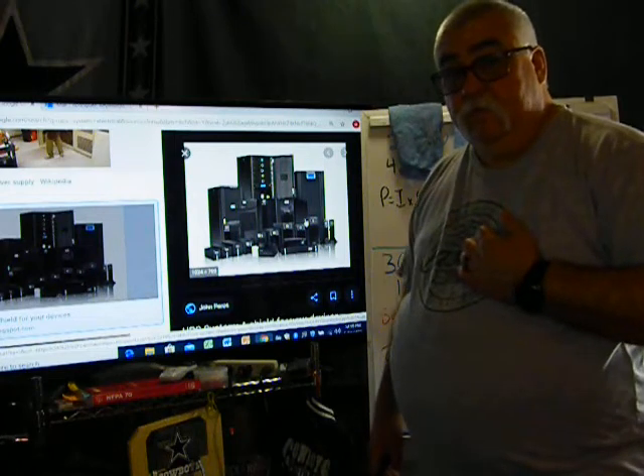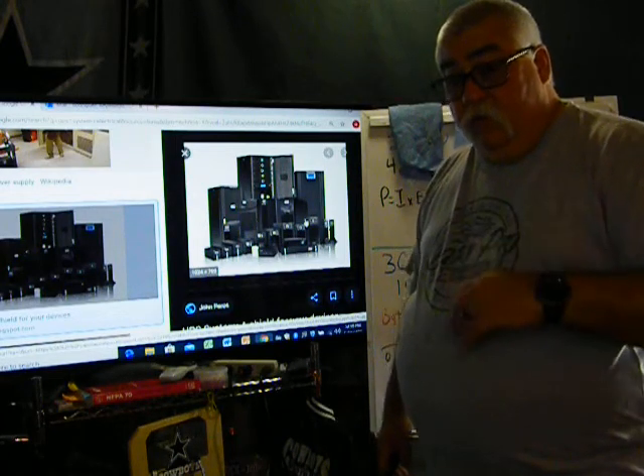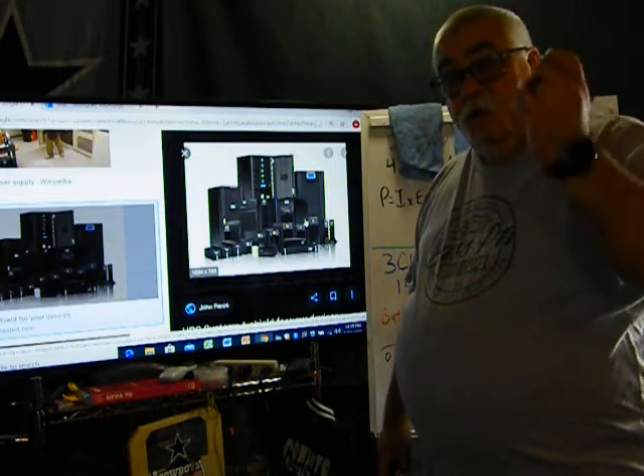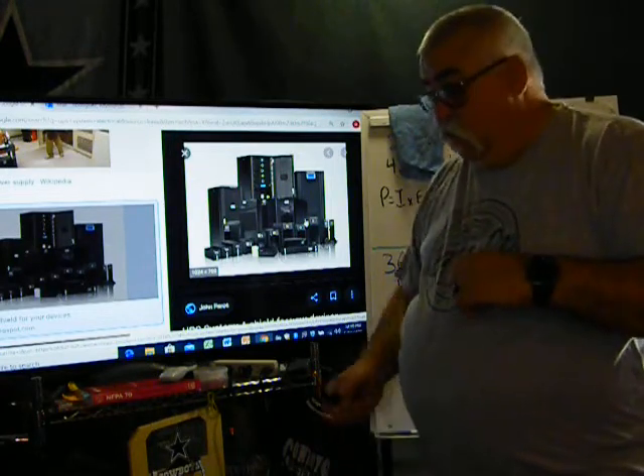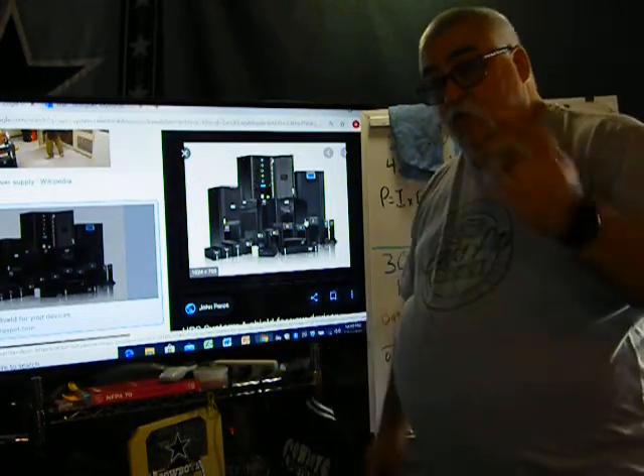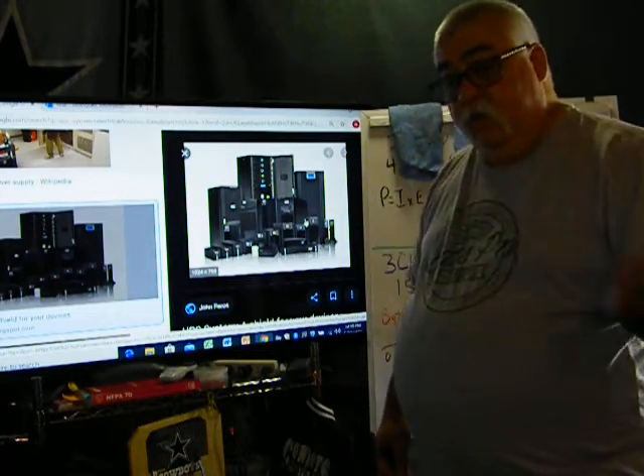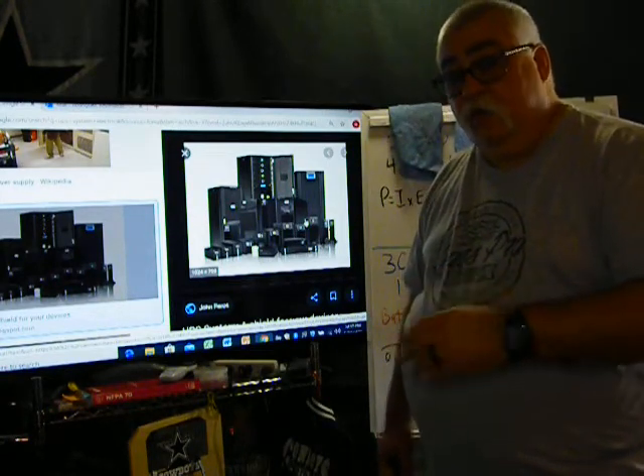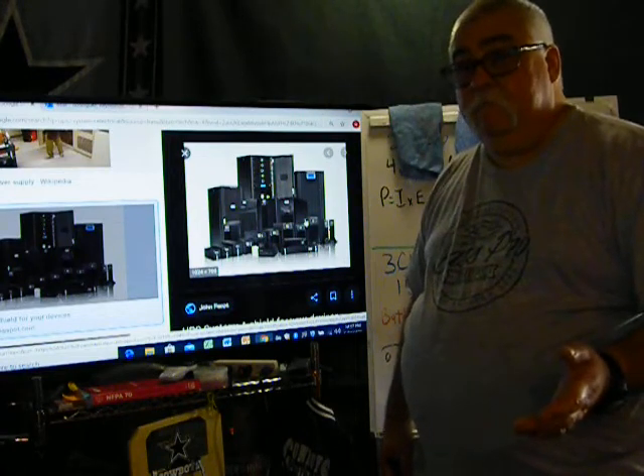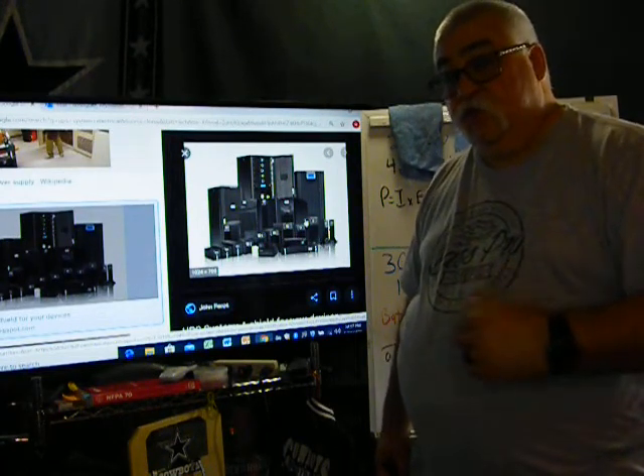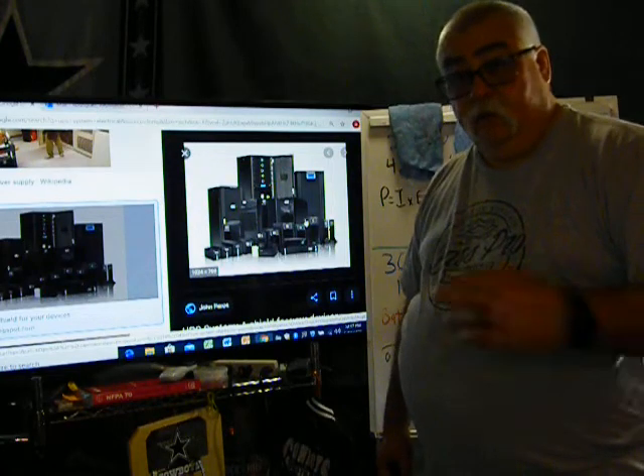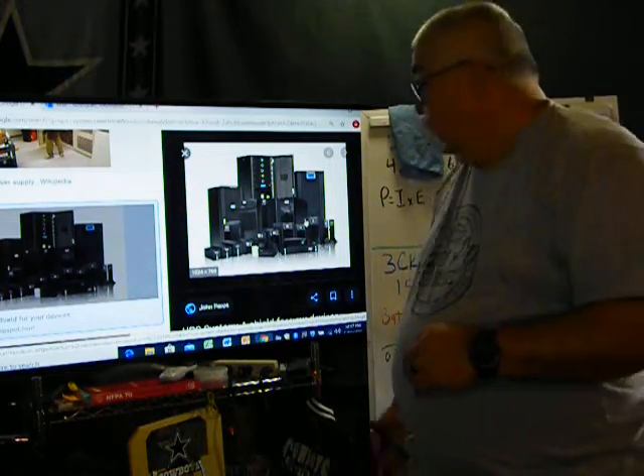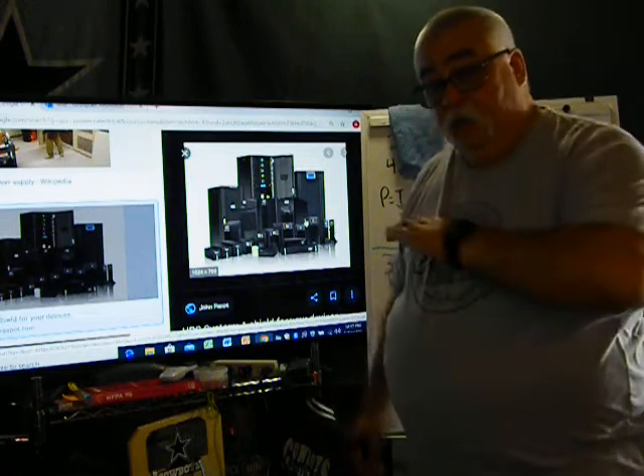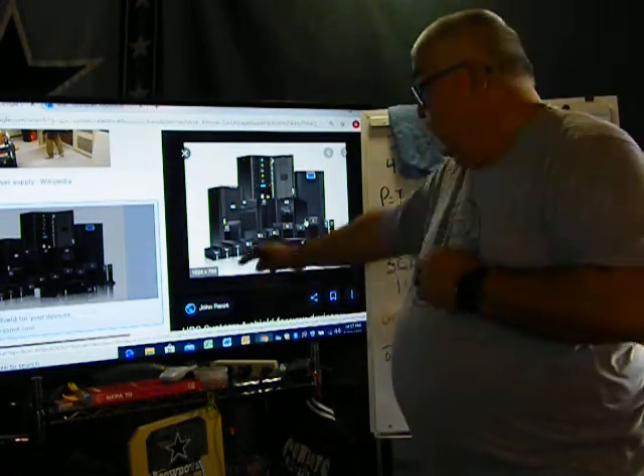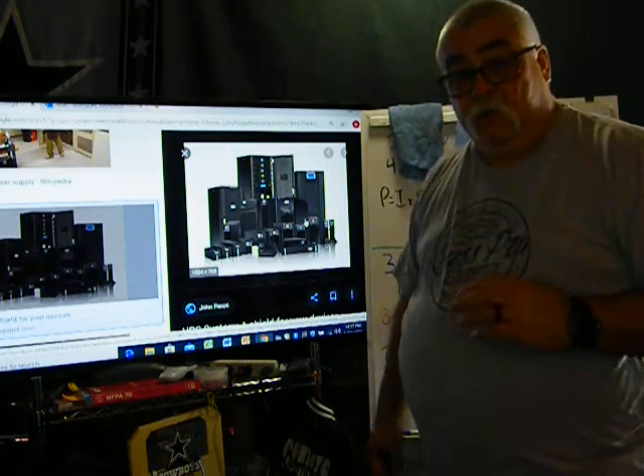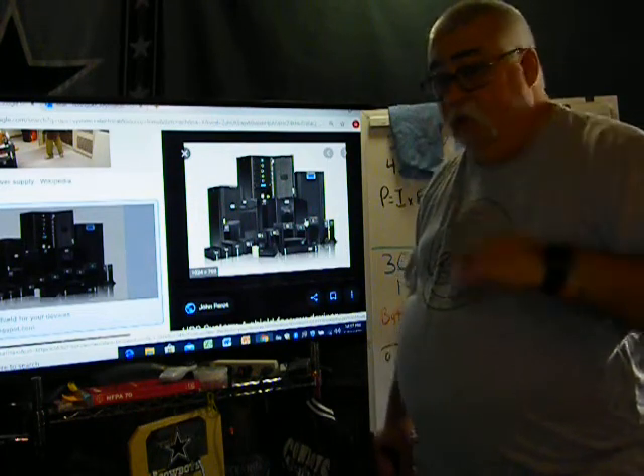We do generator tests. So when we do the generator test every month, because they're plugged into normal power, when we switch over, that power going off and power coming on, that computer or that piece of equipment could shut off. And sometimes they say it takes longer to turn it back on than it does for it to go off. So they put a UPS in to handle that on, that off. Why? Because the UPS power is always there. So if power blinks, it's not going to change it.